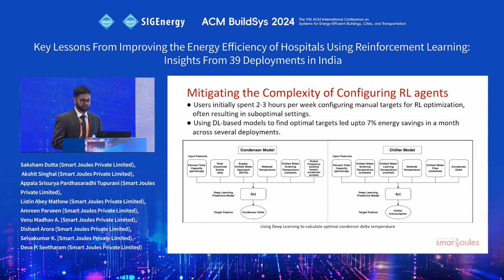We introduced deep learning models to predict optimal settings. For example, we trained a model to estimate possible condenser delta temperature based on environmental parameters like percentage capacity, TDS, SCTA, and wet bulb temperature. Then we used another model to predict chiller consumption for various condenser deltas. By testing different deltas, we identified the target that minimized the chiller energy consumption. This strategy applied in data-rich sites resulted in up to 7% savings across deployments.